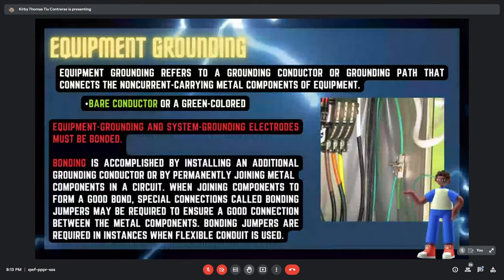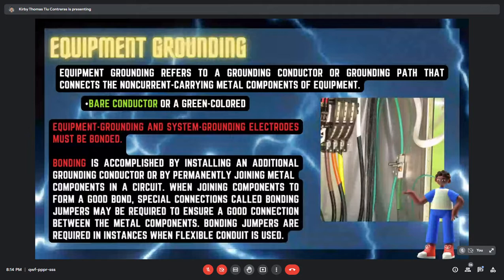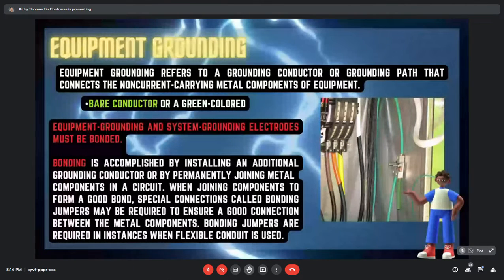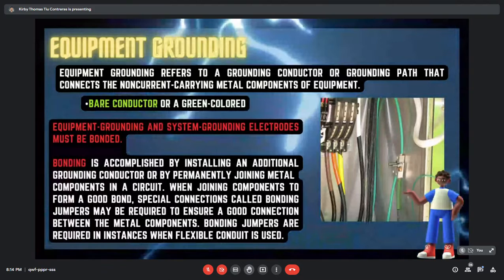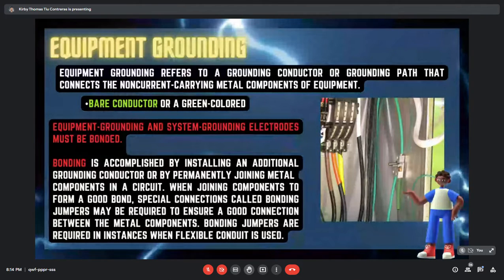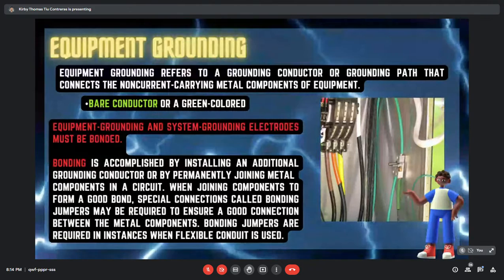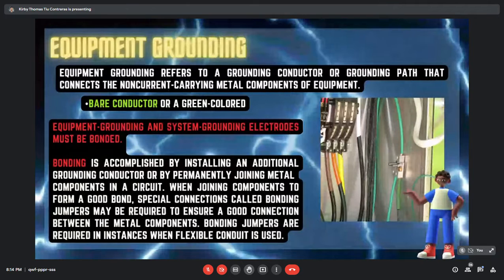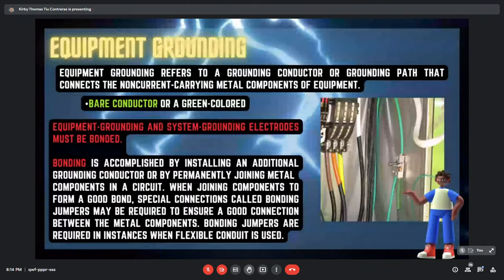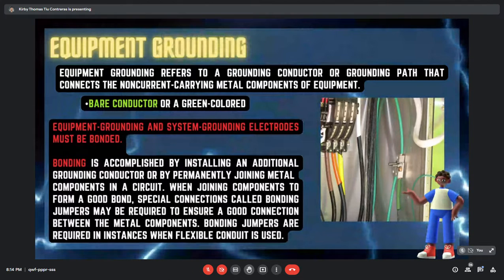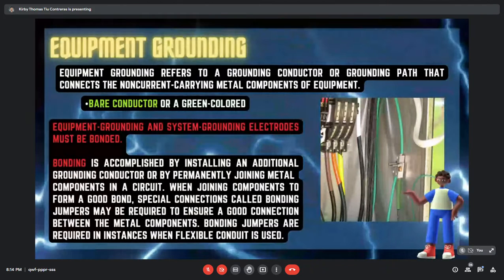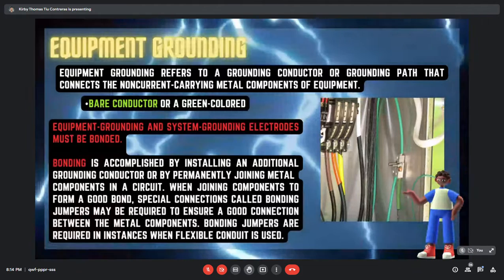So moving on to equipment grounding. Equipment grounding refers to a grounding conductor or grounding path that connects the non-current carrying metal components of equipment. Equipment grounding can be identified as a bare conductor or a green colored one. The green one on the right side is attached to the metal housing or cabinet.